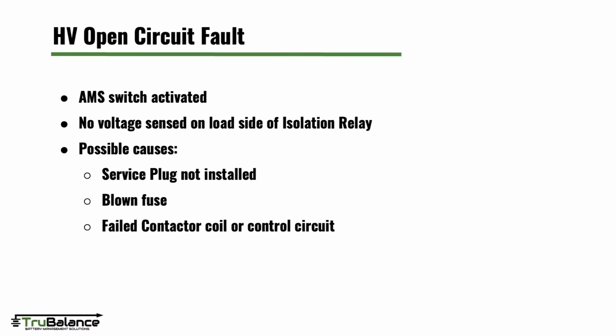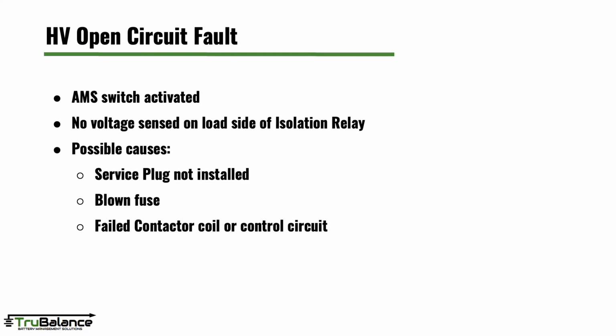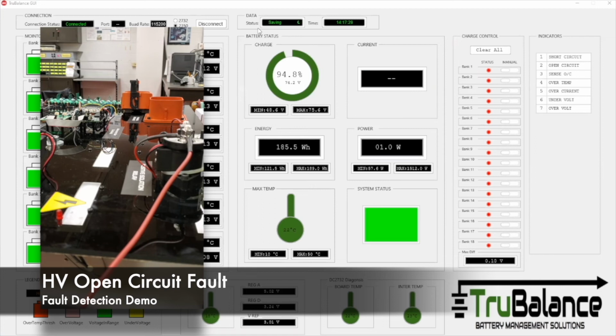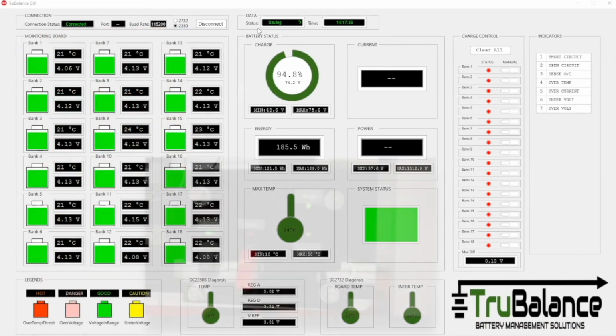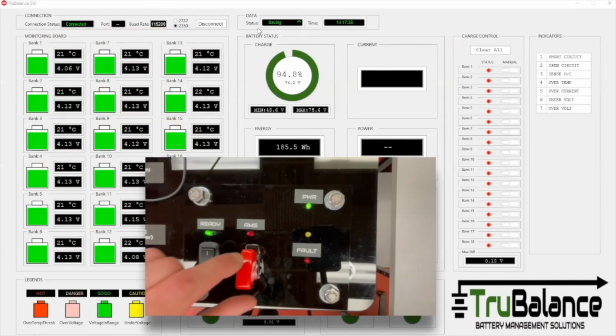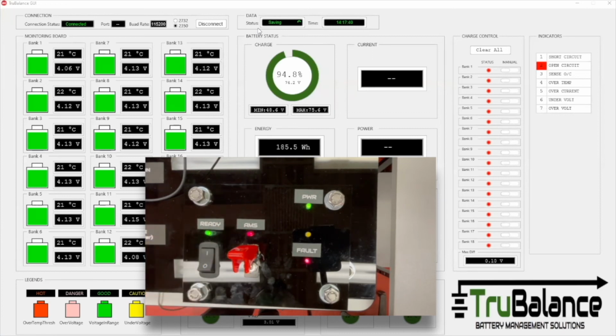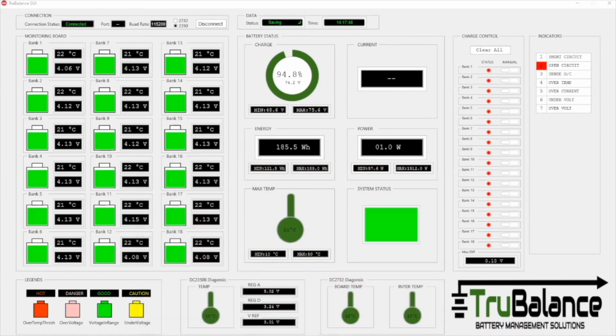An open circuit is detected through comparison with the load side voltage sense. In this demo, we have left the manual disconnect plug uninstalled to simulate the open circuit. If no voltage is sensed on the load side once the isolation relay command has been sent, the isolation relays will be commanded open, the fault light will be illuminated, and the tractive mode will be made unavailable until the system is manually reset following an inspection.